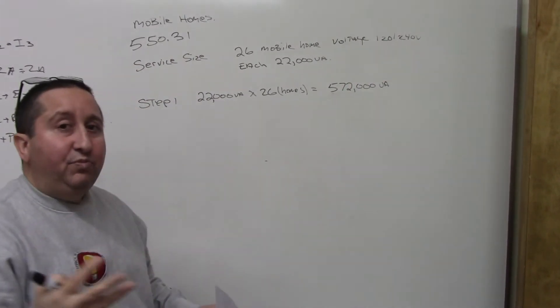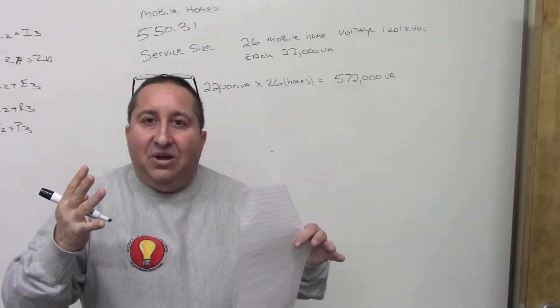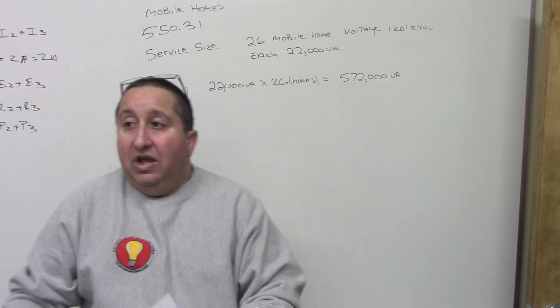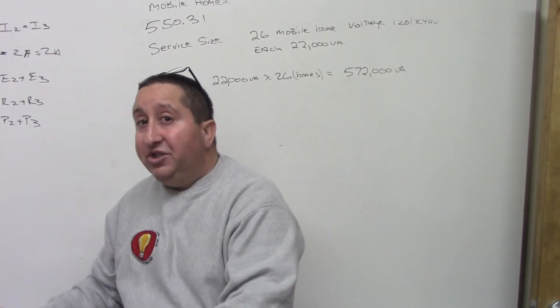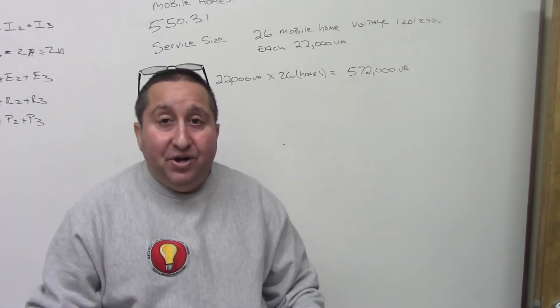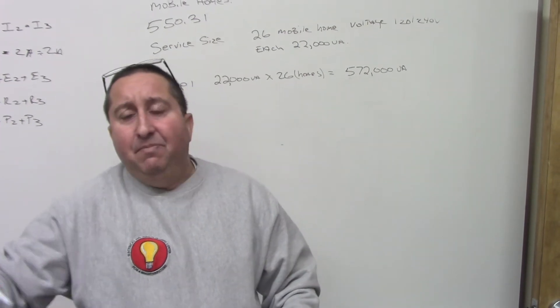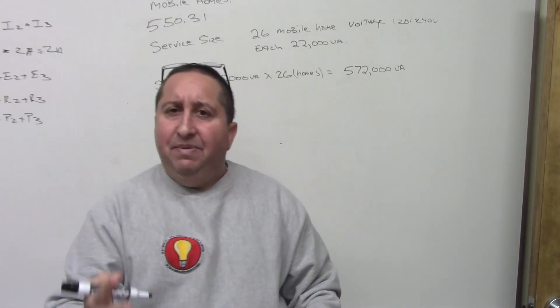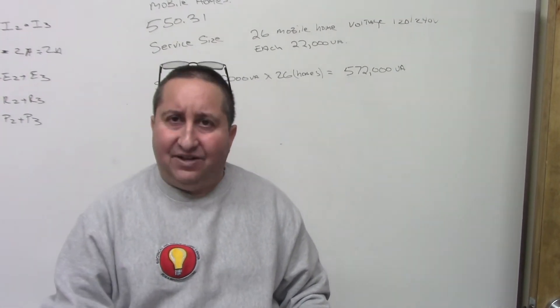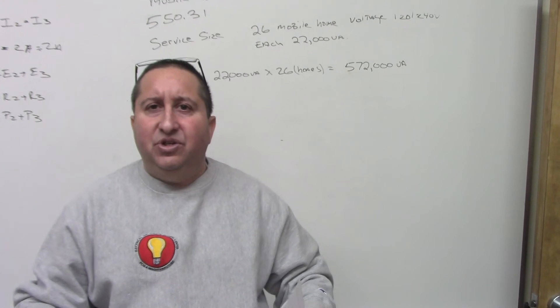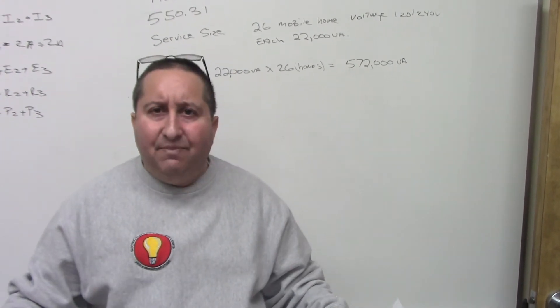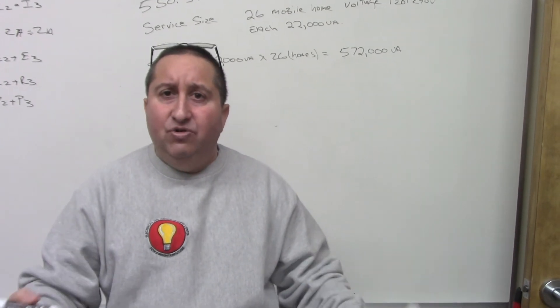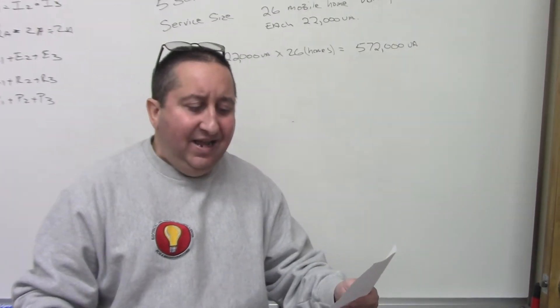Now, I got a stupid question. Is everything going to be on at the same time for these 26 units? That means, is everybody going to be doing the wash at the same time? Are people going to put the lights on at the same time? No, people might go on vacation. Some people might work during the day. So you're going to have a demand factor, because not all 26 units are going to be using 22,000 volt amps at the same time.